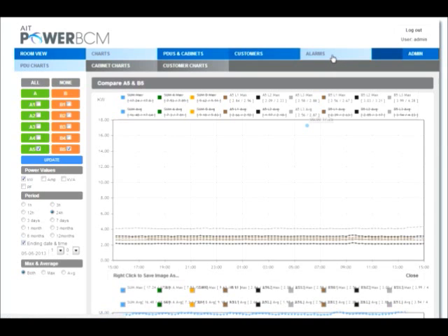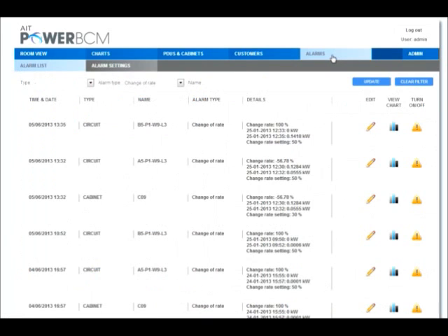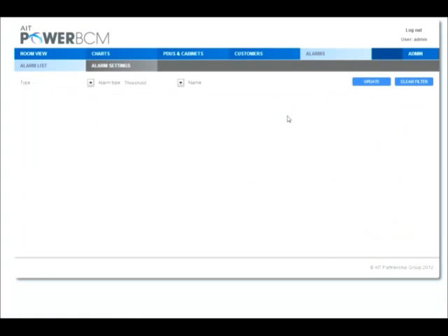There is also an alarm function, and for all of the loads, the thresholds, you can set alarms. There's also a change of rate alarm, which can warn you where there have been changes in load in particular cabinets. At the moment, this system is only showing rate of change alarms. We have had no threshold exceptions. Again, by simply selecting that, I can filter that and see that I have no threshold exceptions for this particular system. Again, reading errors are something that are often useful to track.